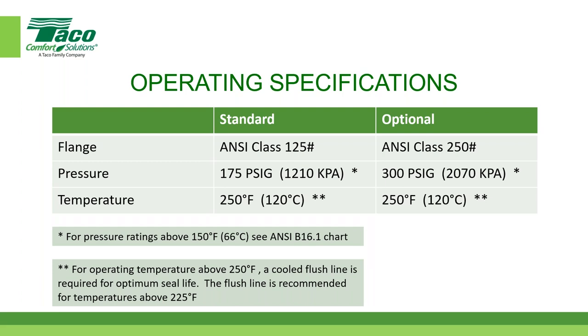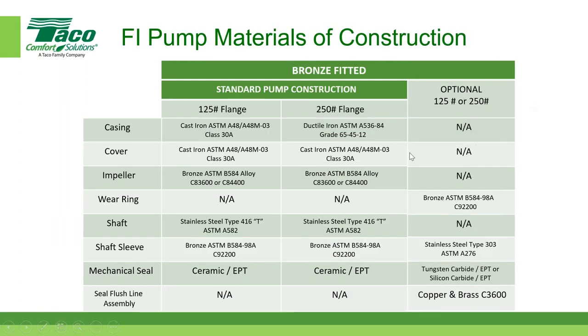They just don't like that temperature. It starts to get out of their bailiwick. So here's some of the material of the constructions, okay? I'm not going to read the whole chart, but I am going to point out some of the differences. We have the different ratings, 100, 125 and 250, while the casing for the 125 is cast iron A48 Class 30A. For the bigger pump, the higher rated pump, with bigger flanges and higher rated pressure, it's actually ductile iron.